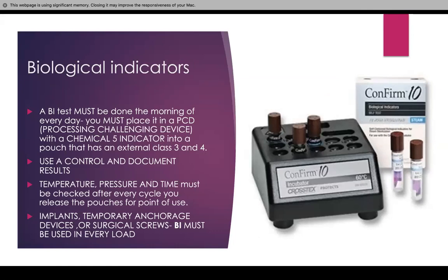Then we are going to pouch it. We are going to label it with the date, time, cycle load, sterilizer used, and the initials — just like any other instrument. Then we are going to place a class 5 indicator. The class 3 and 4 are already on the pouches. We have to use a control and document the results.